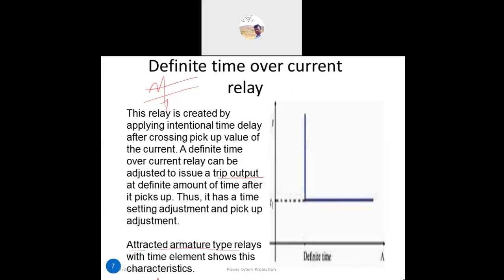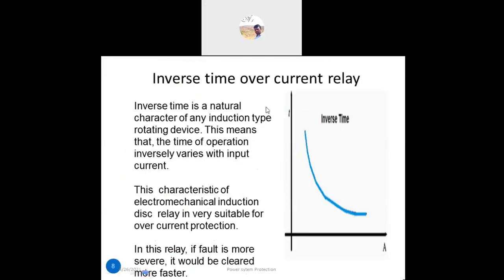Next is the inverse time overcurrent relay. This is the natural characteristic of any induction-type rotating disc. The time of operation inversely varies with the input current. These characteristics of the electromechanical induction disc relay are very suitable for overcurrent protection.